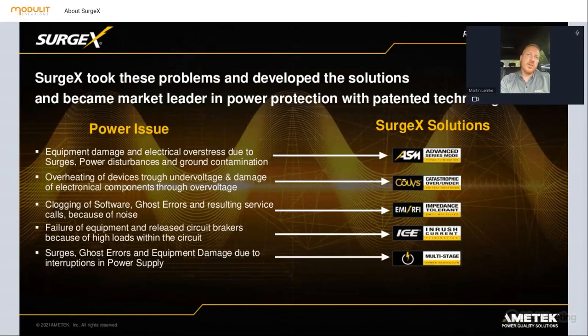The second technology we invented is catastrophic over and under voltage shutdown. Whenever there's a high voltage event - for example when a blower motor is started, there could be an under voltage where the voltage drops to 170 or 160 volts, or when it's switched off, there's too much voltage in the line.